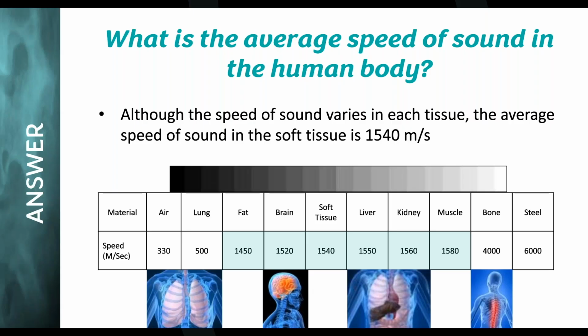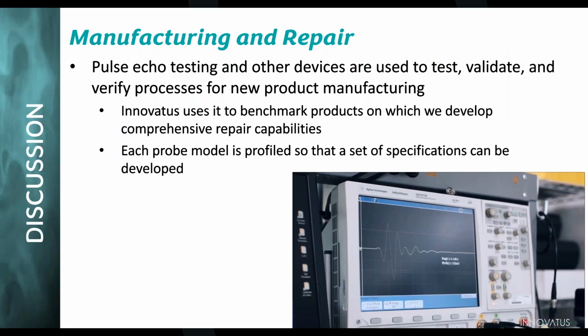And the reason that's important is, we talk about image quality and the OEMs talk about number of channels, number of elements in a probe. You can't beat physics. Physics is a law, and it's inviolate. When we talk about physics, we're sending beams of ultrasound into the body, constantly interrogating the body to create those cool images that we see. You can only do that so many times where you can display that image in real time. If you try and send too many lines, it takes too long. Even at 1540 meters per second, which sounds really fast, and it is, we're doing it hundreds and thousands of times a second. And so you can only do so many lines. And you can skip over that. Yeah. All right.